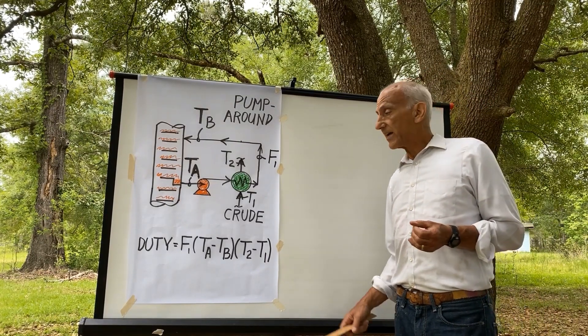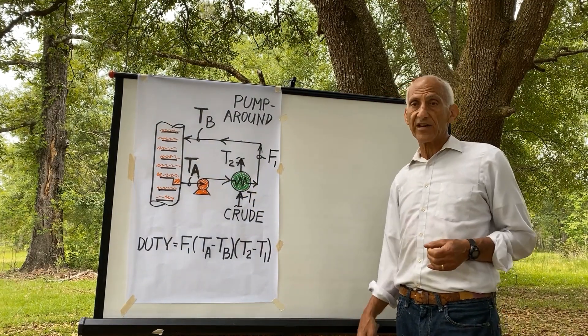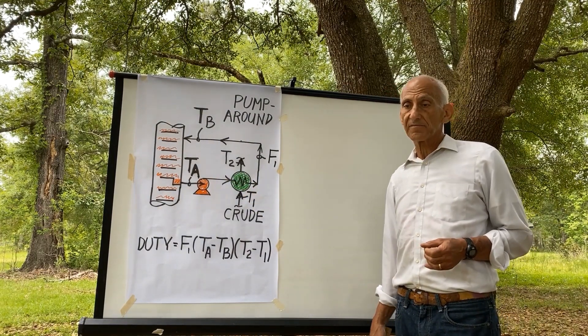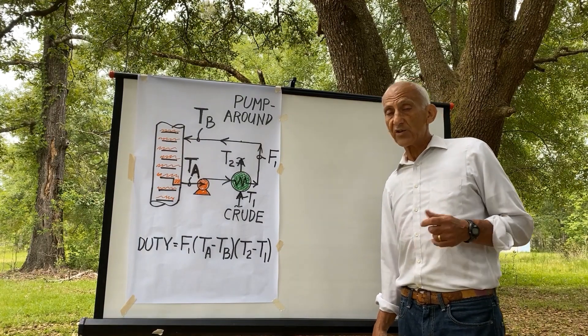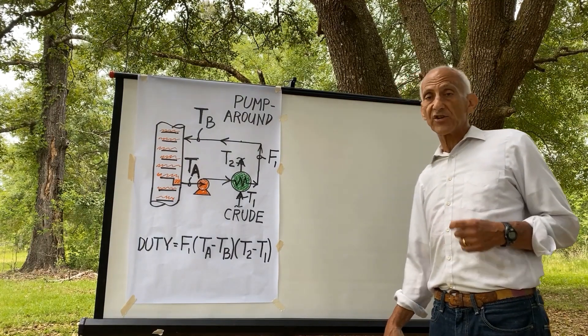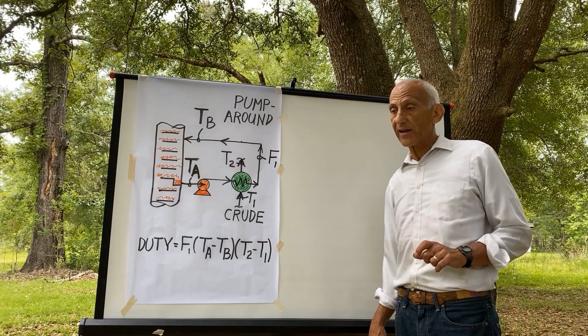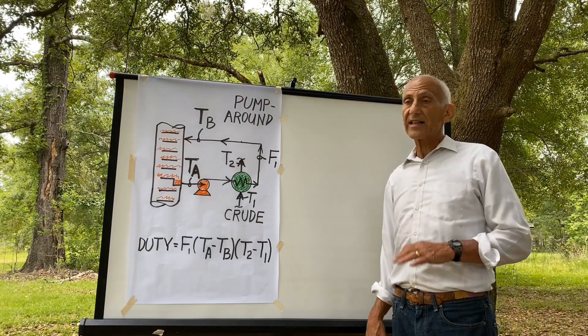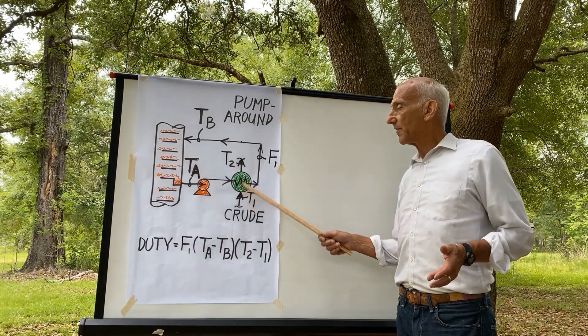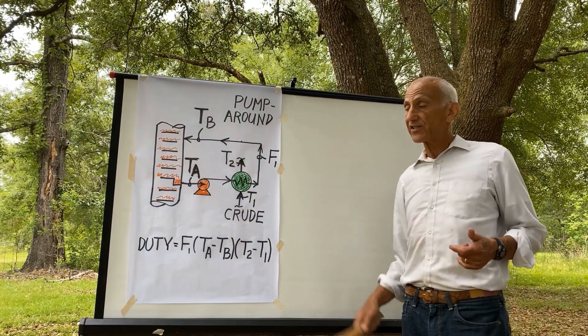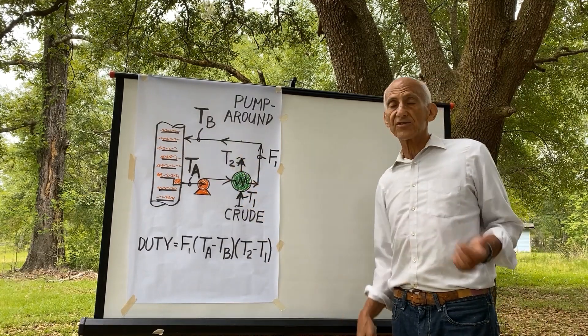We say you are limited by the surface area of the exchanger. There's no way to tell for sure whether increasing the pump around circulation rate extracts more or less heat — it's kind of like 50/50. You have to look at the change on the other side, in this case the crude side. If this temperature change goes up, then increased pump around circulation rate is fulfilling your intended function.